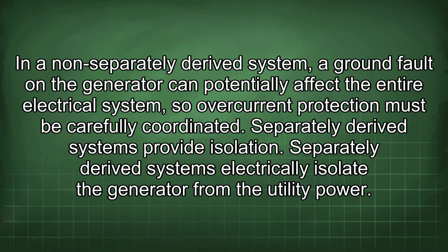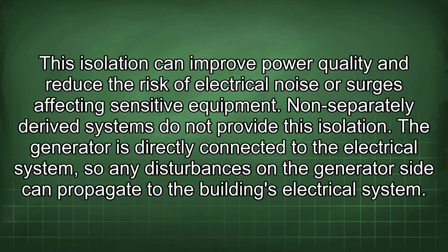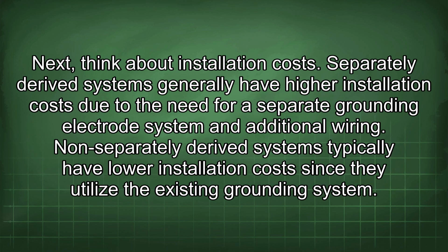Separately derived systems provide isolation. Separately derived systems electrically isolate the generator from the utility power. This isolation can improve power quality and reduce the risk of electrical noise or surges affecting sensitive equipment. Non-separately derived systems do not provide this isolation. The generator is directly connected to the electrical system, so any disturbances on the generator side can propagate to the building's electrical system. Next, think about installation costs.